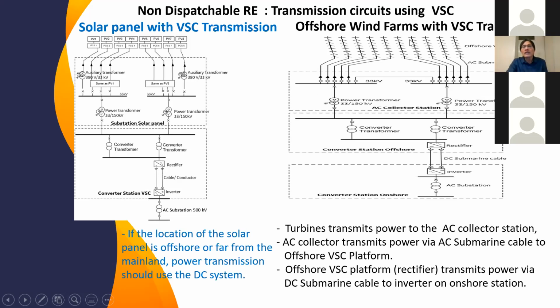The same for turbines, a cluster of turbines. We connect through a submarine cable to the AC collector station. From the AC collector station, we send the power to the converter transformer and then connect to the rectifier. And then from the rectifier, we use a DC submarine cable to transmit energy to the inverter, which is located in the AC substation.